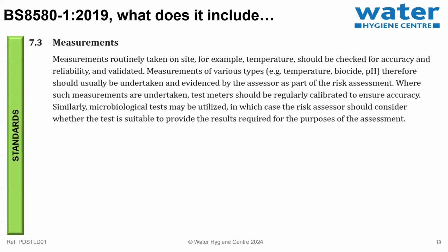So simple takeaways for the day are: keep the hot hot, keep the cold cold, keep it all moving, keep it clean, and keep it well managed. So keeping it hot hot, above 60 degrees C from a stored capacity, above 50 degrees C from a distribution system and return. Keep the cold below 20 degrees C within a minute. Keep the hot 50 degrees C. Keep the cold less than 20 degrees C.